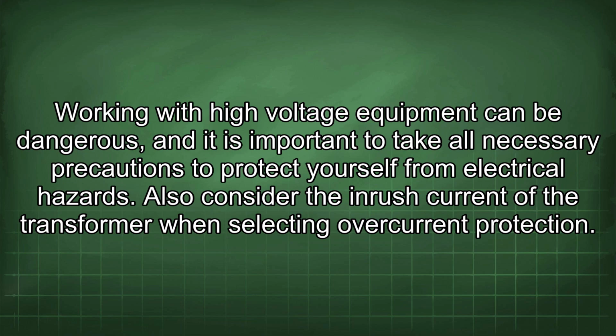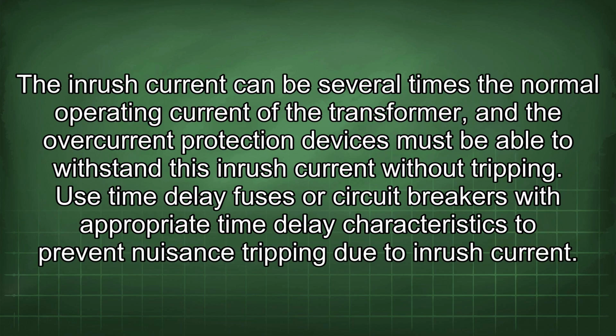from electrical hazards. Also consider the inrush current of the transformer when selecting overcurrent protection. The inrush current can be several times the normal operating current of the transformer, and the overcurrent protection devices must be able to withstand this inrush current without tripping. Use time delay fuses or circuit breakers with appropriate time delay characteristics to prevent nuisance tripping due to inrush current.